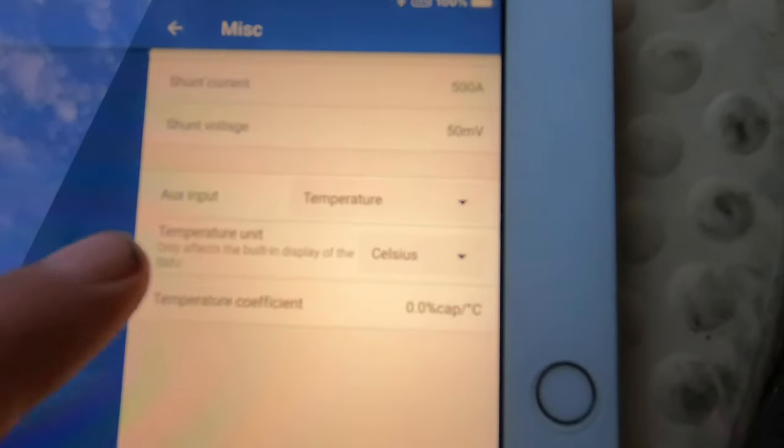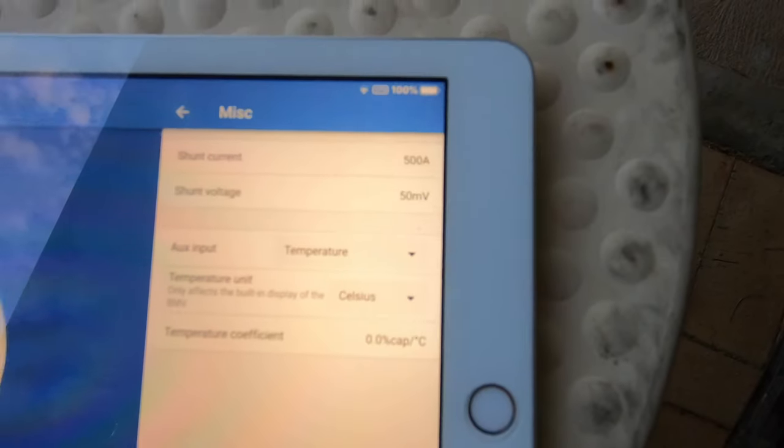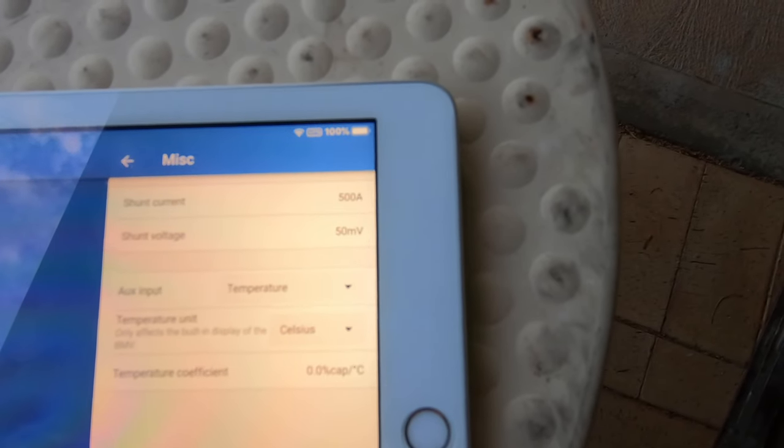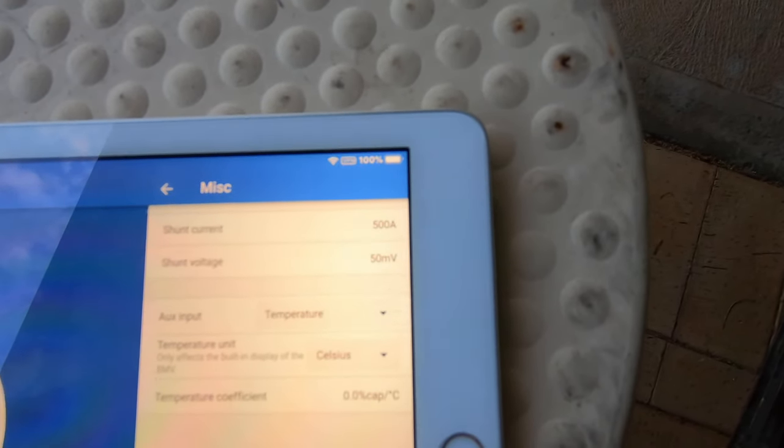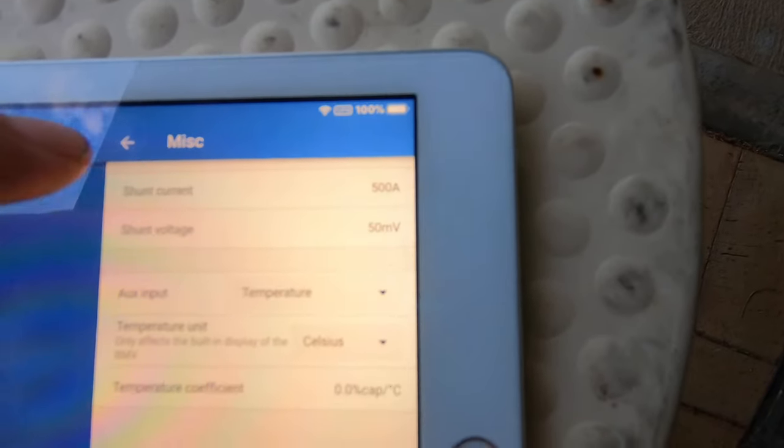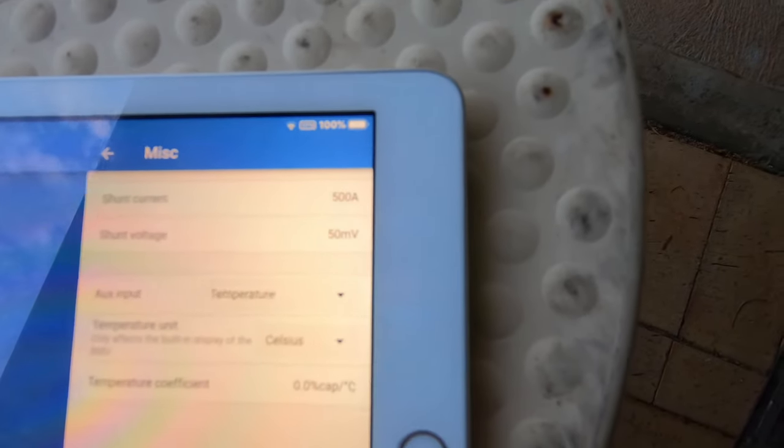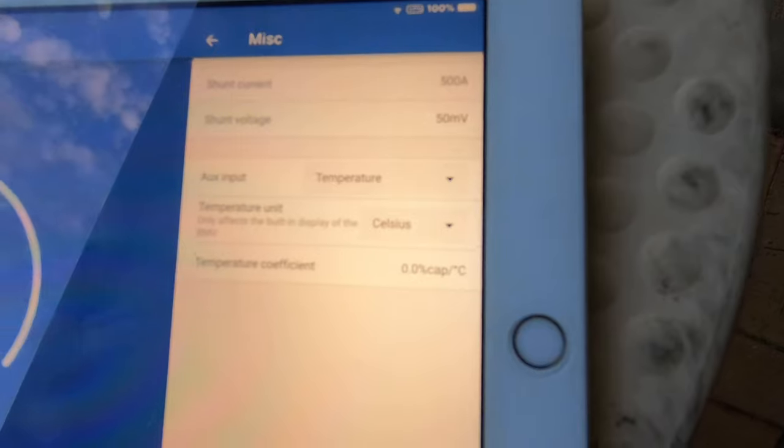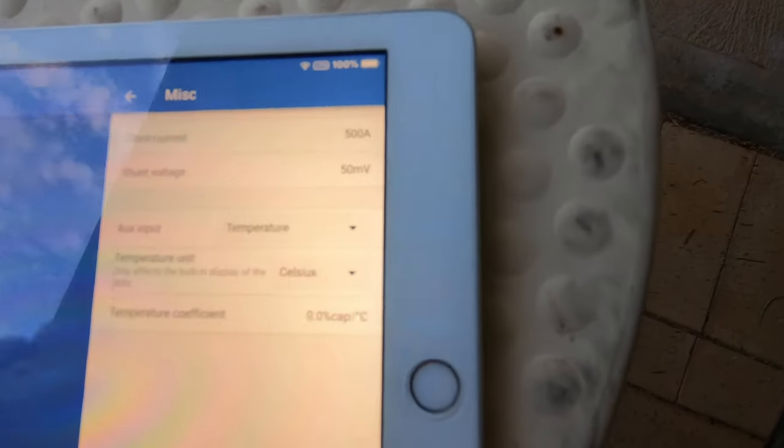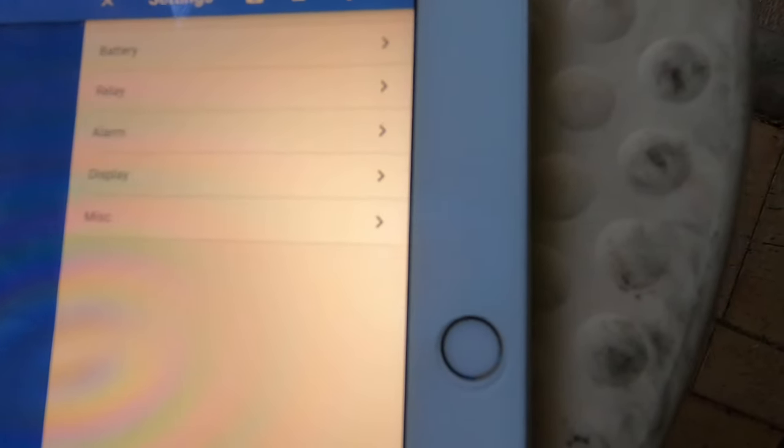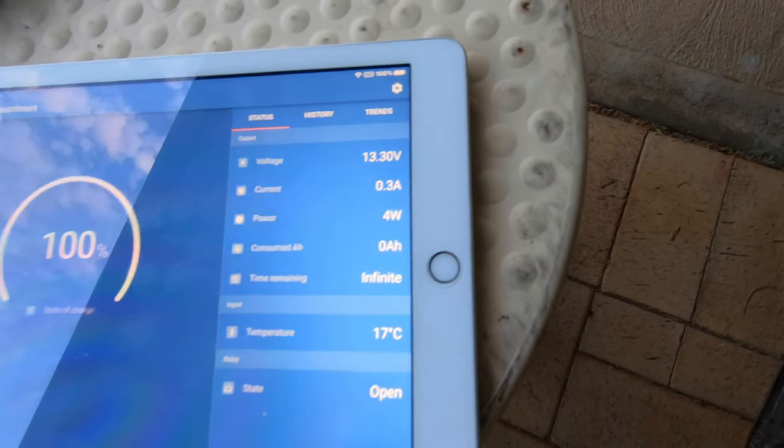If you have a temperature sensor, in the miscellaneous you've got auxiliary input, set that to temperature. That's the shunt, the type of shunt I have, a 500 amp 50 millivolt. That's all got to be set right.